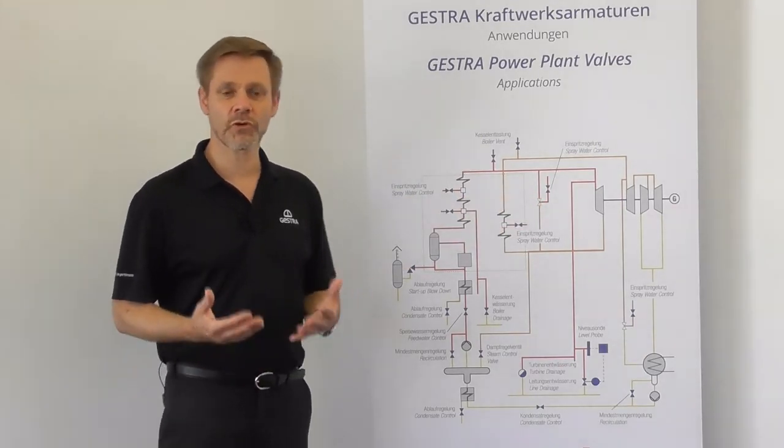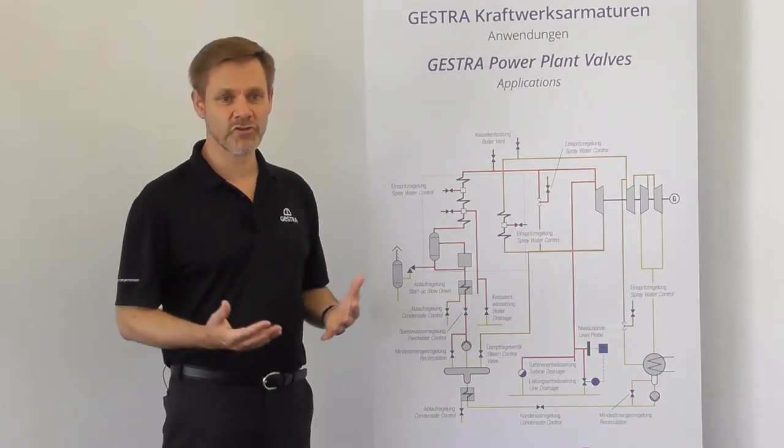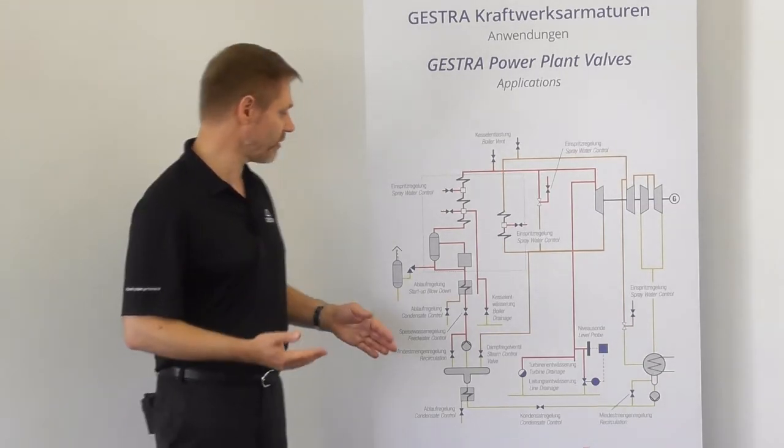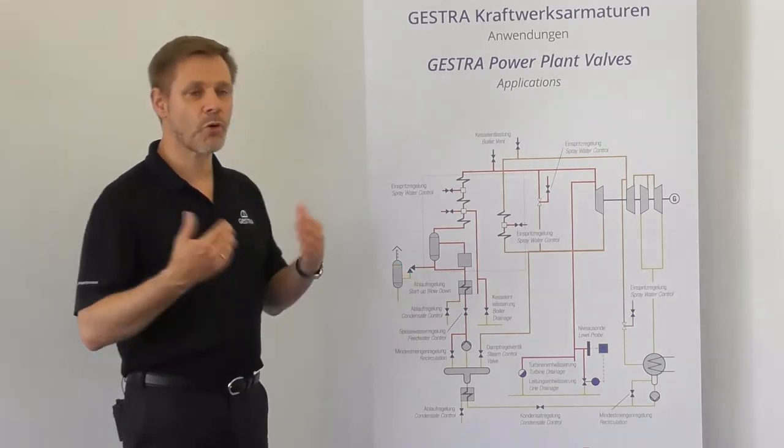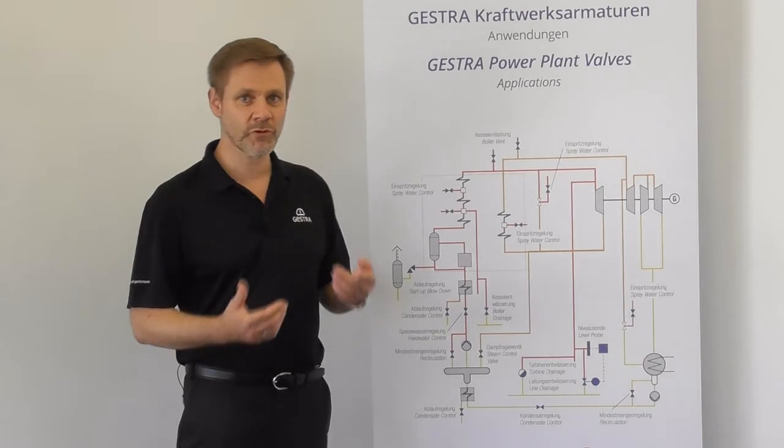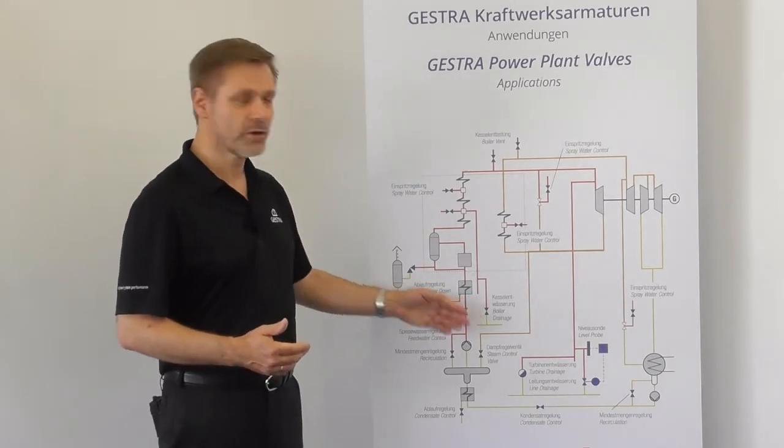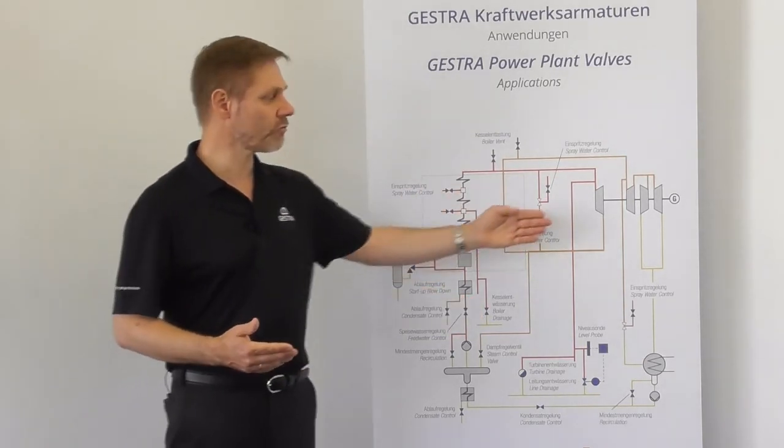Applications for severe service at flashing water are for instance the start up blow down valves of the boiler drum, then all drain and warm-up valves for the boiler, for the piping system or for the turbine plant.